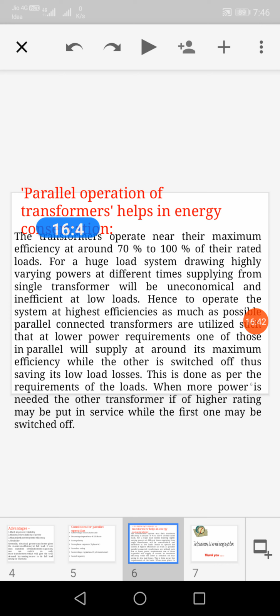And if load sharing is not done, the transformer gets overloaded. Maximum availability of power: in case any one transformer from a set of transformers operating in parallel is taken out for maintenance, a total interruption of power is avoided. The other transformer in parallel continues service. And how about maximum power system efficiency? Electrical power transformers operate at full load efficiency when they are fully loaded. When a number of transformers are run in parallel, it is possible to use only those transformers which can serve the total demand by operating close to their rated capacity.